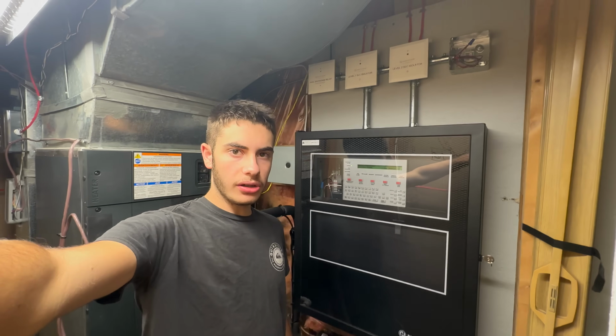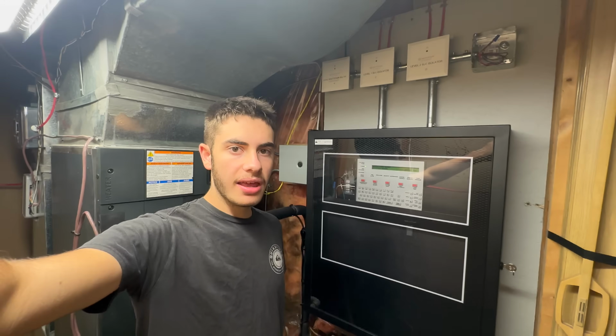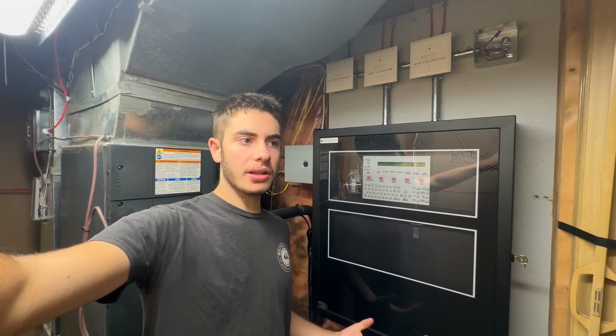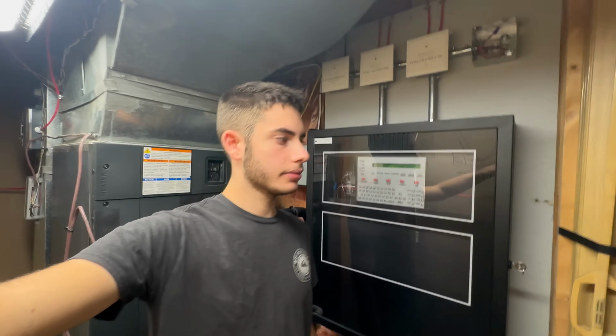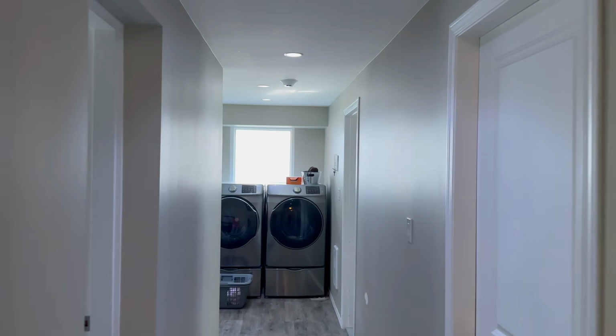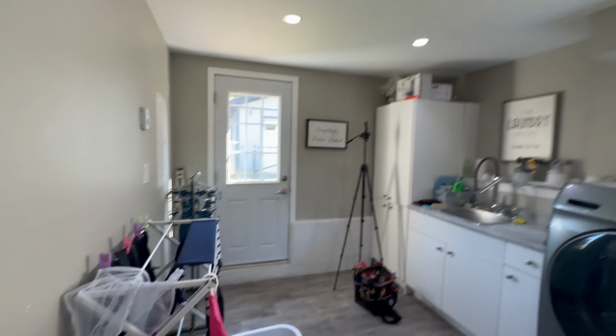All jokes aside, my plan in this video is to add another pull station to my home fire alarm system. For those of you that aren't familiar with it, I installed a Notifier addressable fire alarm system in my home to offer better protection than what the residential smoke alarms offer, and more customization and more ability to do things the way I want them done. When I originally installed the system, we installed smoke detectors and sounders and horn strobes, but we only did the one pull station at the front entry, and this is sort of one of the major entrances to the house.